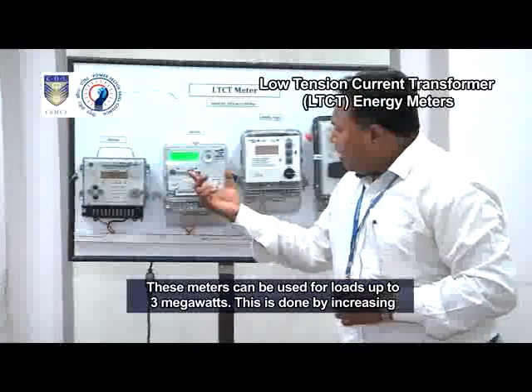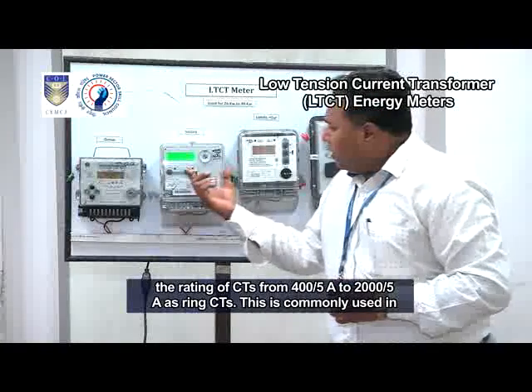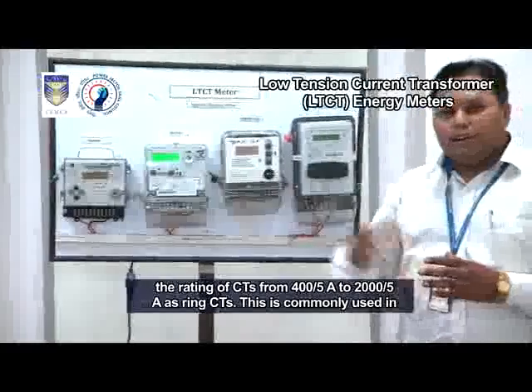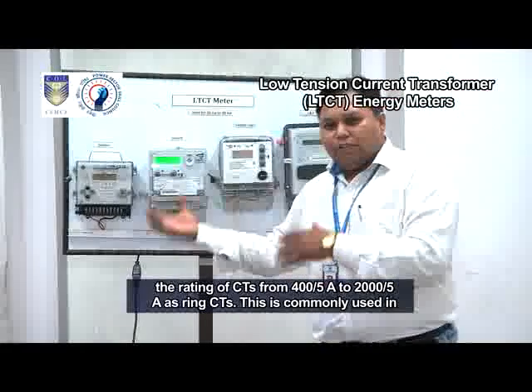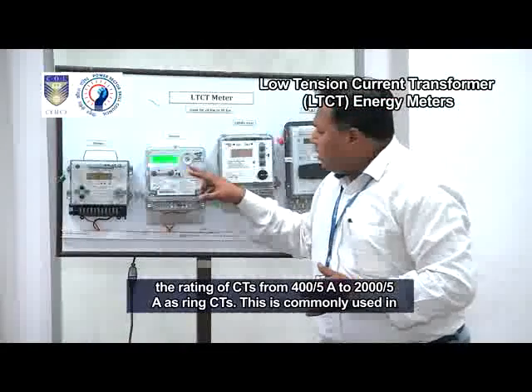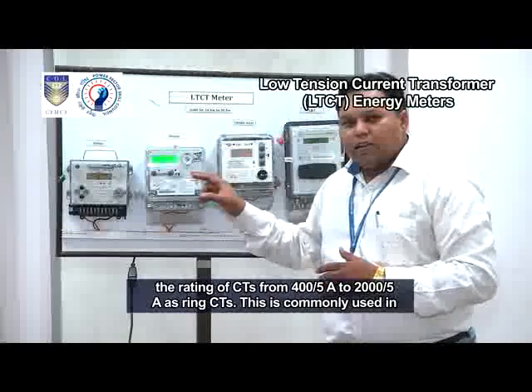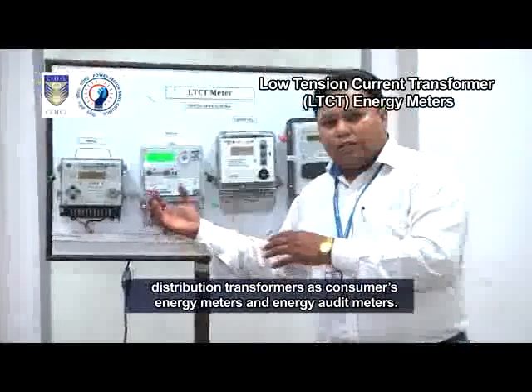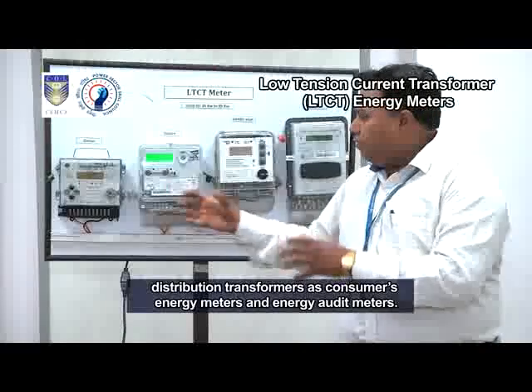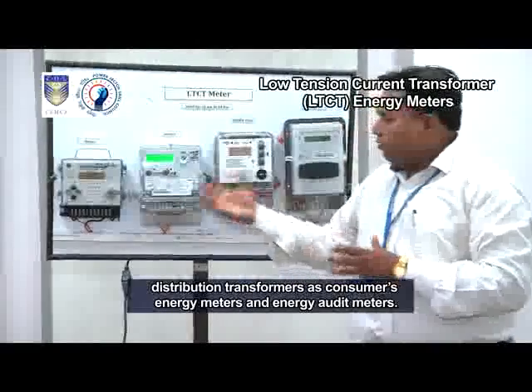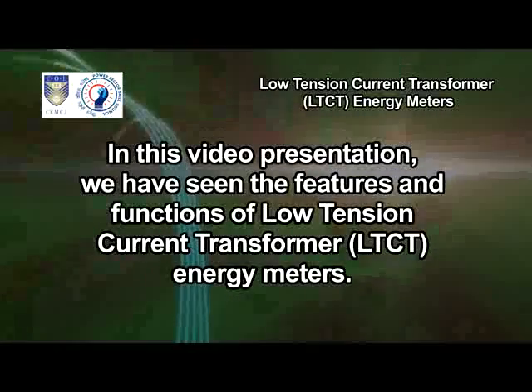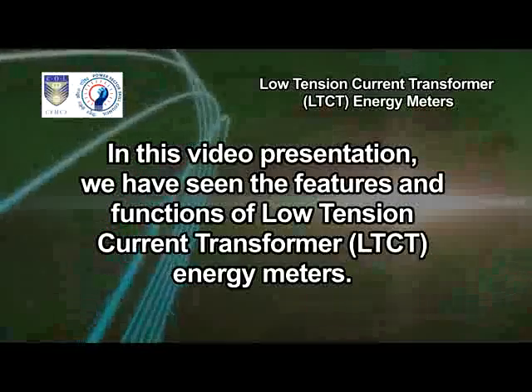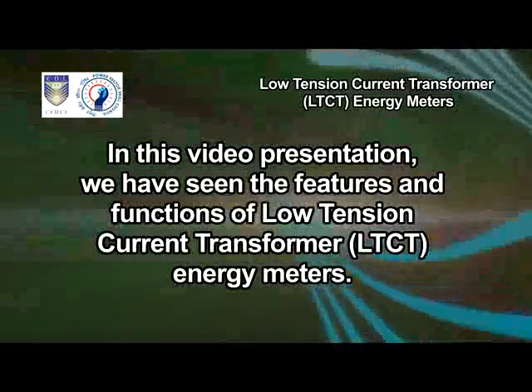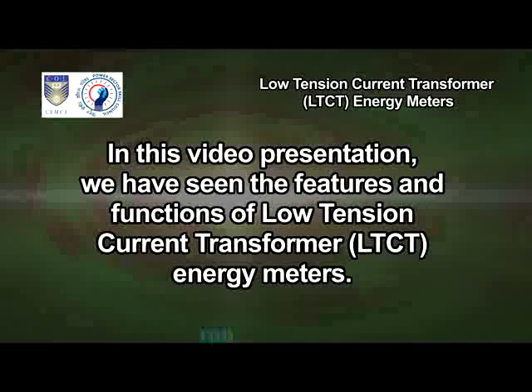This is done by increasing the rating of CTs from 400 by 5 ampere to 2000 by 5 ampere as ring CTs. This is commonly used in distribution transformers as consumers' energy meters and energy audit meters. In this video presentation, we have seen the features and functions of low tension current transformer LT-CT energy meters.